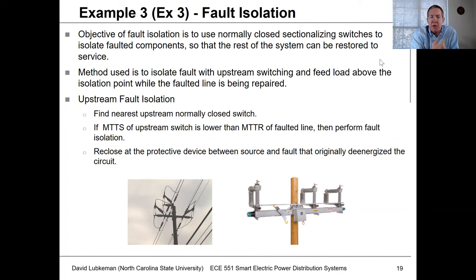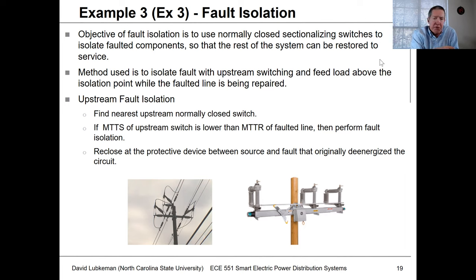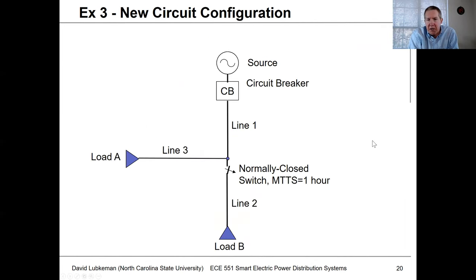The way this would work is if there was a fault, I would look for the nearest upstream switch and open it up. If it turns out I can get that switch quickly — at least in less time than it would take to repair the section — then if I had an upstream protection device I would close that and restore service to the rest of the system.